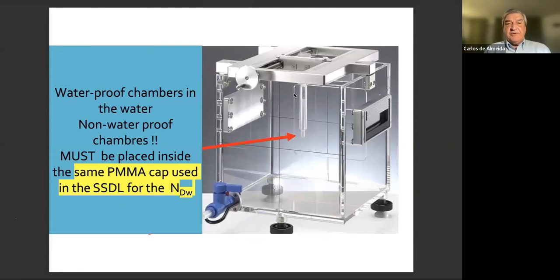Then you must remember, it's very simple, but I think I should mention that when the chambers are sent to the calibration lab, if they are waterproof chambers, they put the chambers in the water at the reference depths and perform the measurements. But if the chamber is not waterproof, it has a PMMA cap that is also used in the SSDL, and you have to use that, okay? So remember that. Don't mess up, because if it's non-waterproof and you put it in the water, you will just destroy the chamber, okay? And just remember that you have to reproduce what the calibration lab provides to you. Next one.